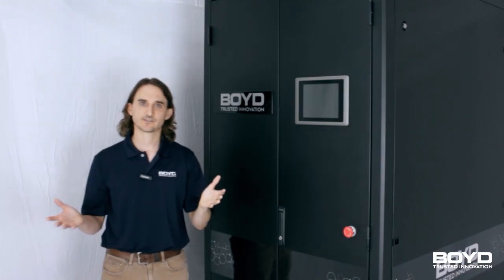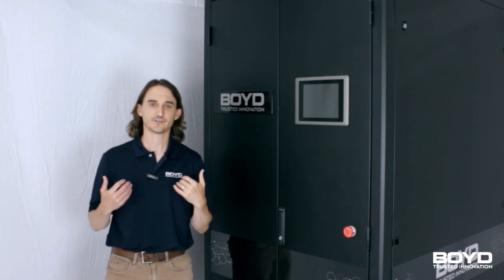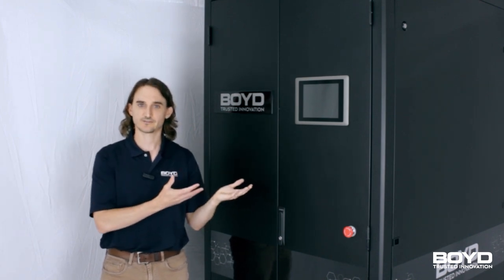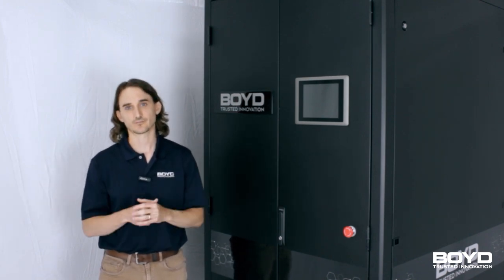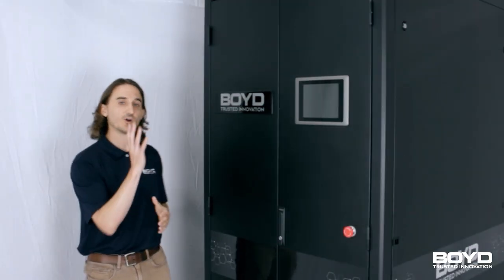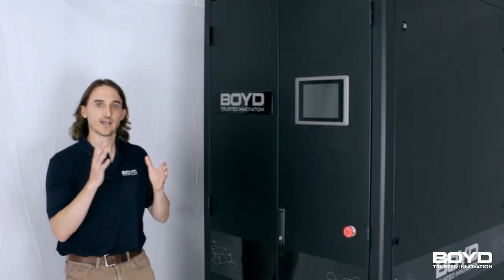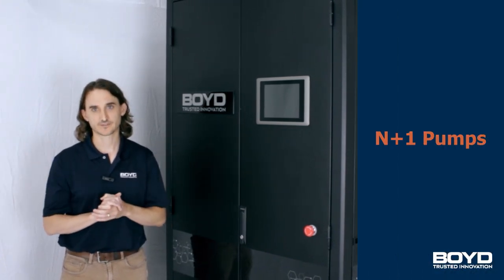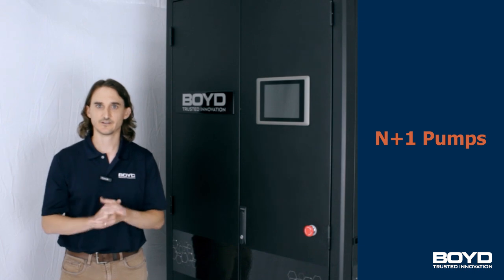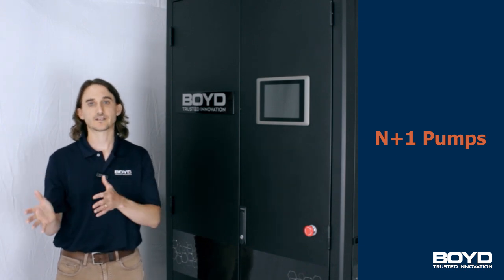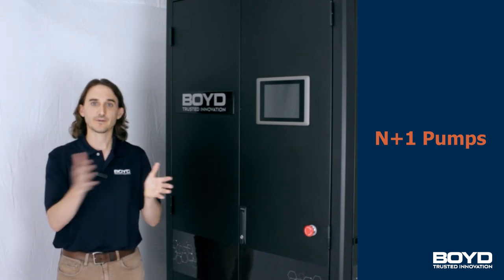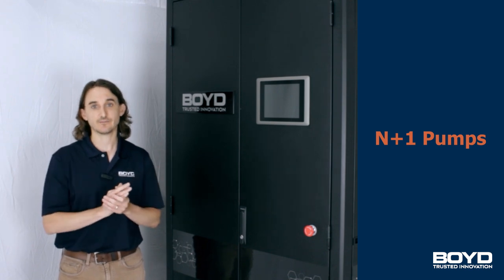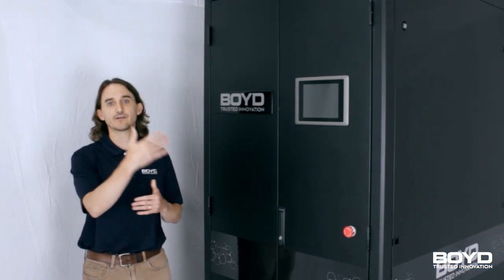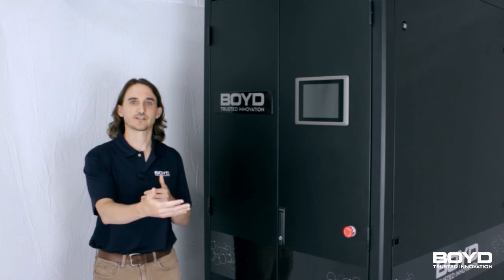Through that interface, the facility has the ability to receive the data, to have visuals into what the system is doing, as well as to control certain parameters. As we go inside the unit, we have the heart of the system, which is 2 30 horsepower pumps. These pumps are redundant. They can run together or separately for swapping capability, as well as easy maintenance. They provide the pressure and the flow to the secondary loop.